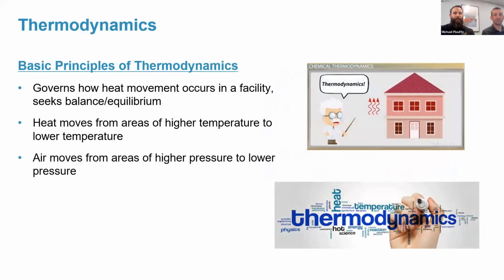I'm going to go over some very basic thermodynamics as it relates to air movement throughout the building. As many of you, I'm sure, know, heat is always going to move from the area of higher temperature to wherever the lowest temperature is. So basically, when you're heating, heat from that conditioned space is going to move to wherever there is no heat, which is typically the unconditioned spaces in the building or outside of the building.